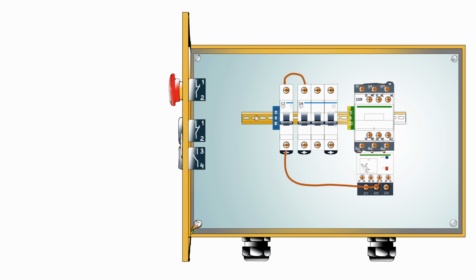So we draw a connection from 96 on the overload relay to 1 on the e-stop button, and then from 2 on the e-stop button we go to 1 on the stop button, and then from 2 on the stop button we go to 3 on the start button. So 3 on the start button is the same connection with 13 on the auxiliary contact. So we connect a cable from 3 which goes back to our contactor, and we connect it to 13.